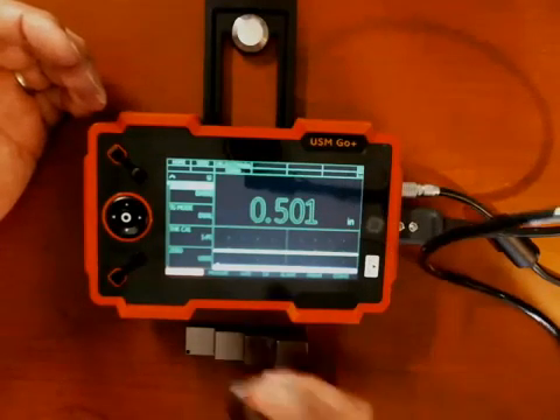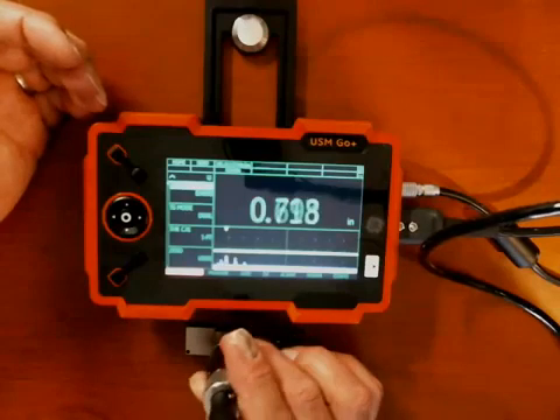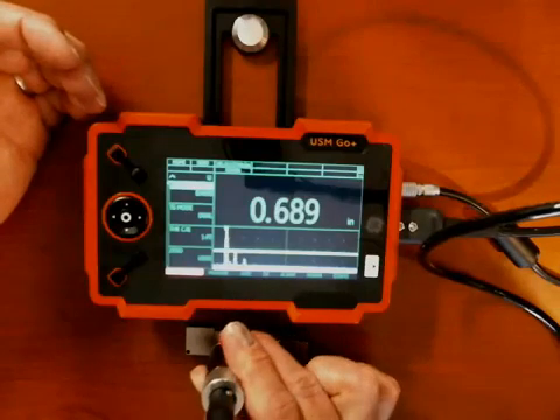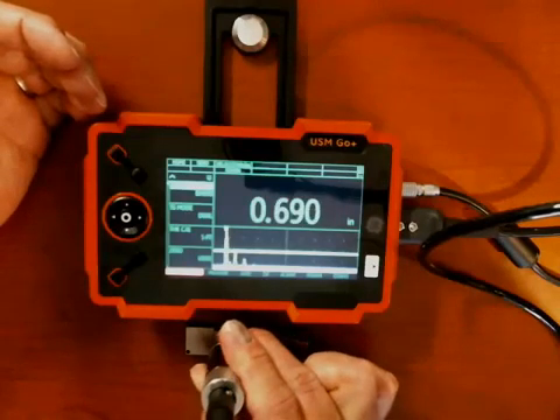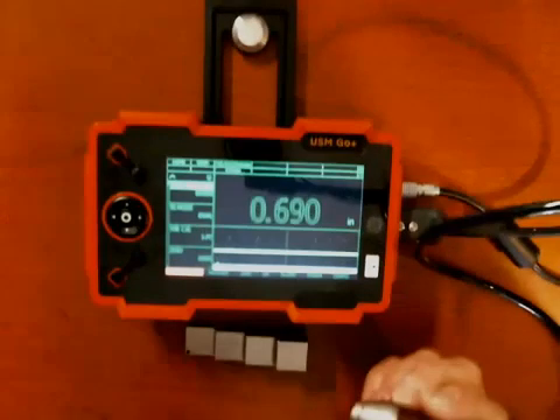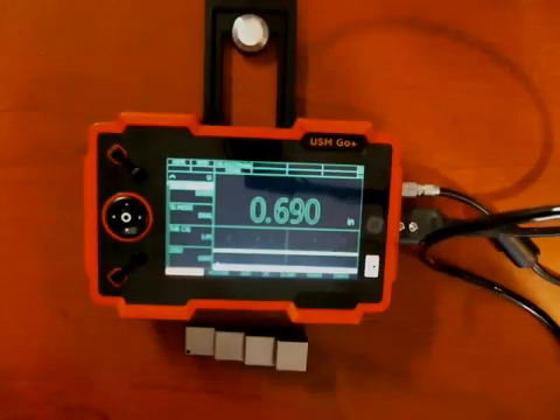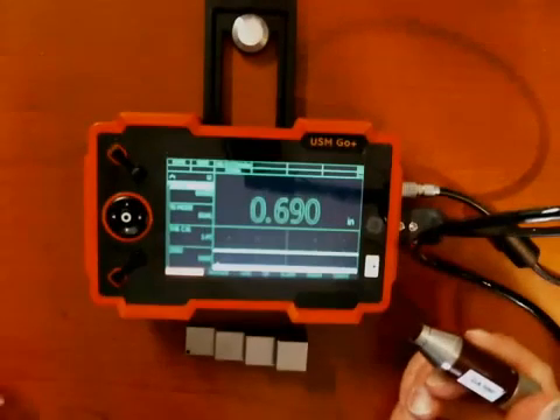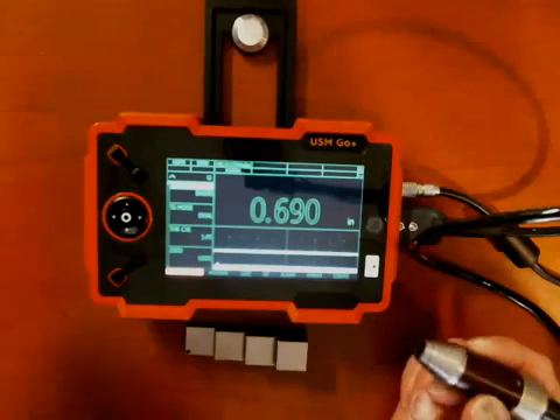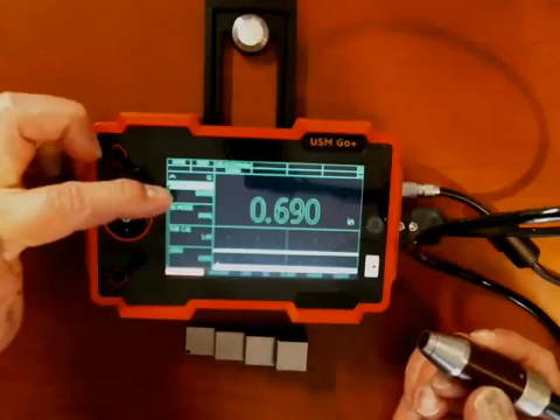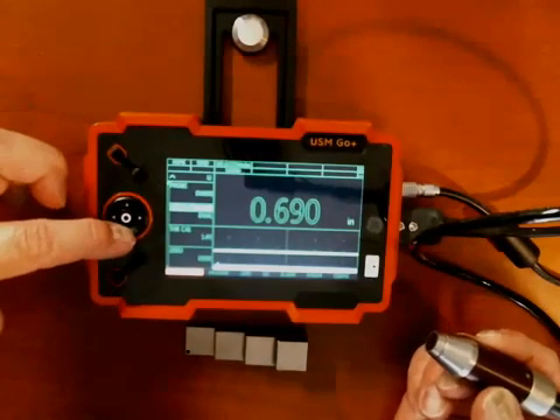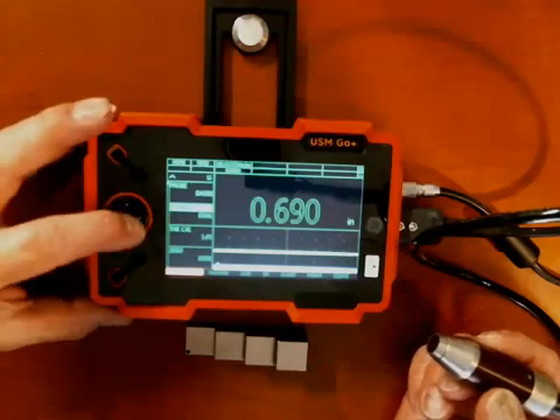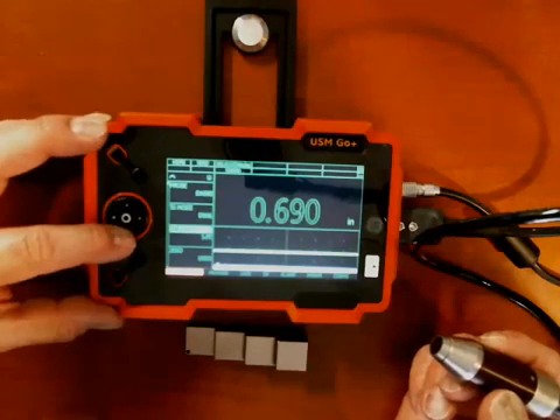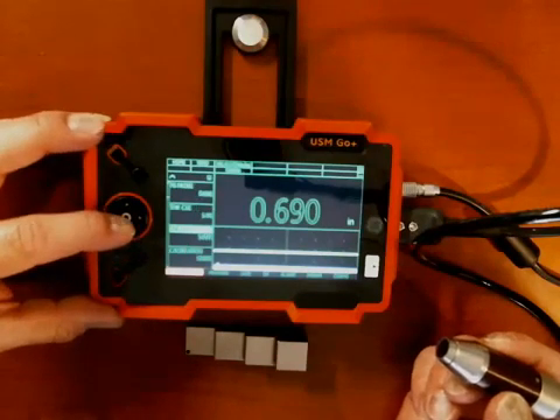Just for the heck of it, I'll take a measurement, and there's my 1/2 inch block, but it's saying 689. What's going on? That's not the right answer. Well, we haven't yet calibrated the instrument and the probe together. If we start out on the probe selection and start going down through the list, I can choose different thickness gauge modes, calibration modes, zero modes.